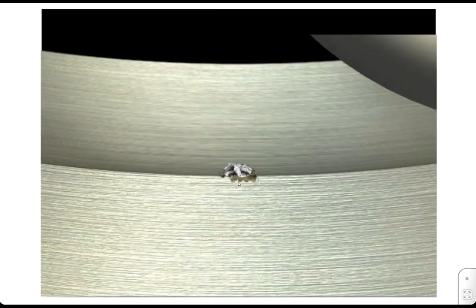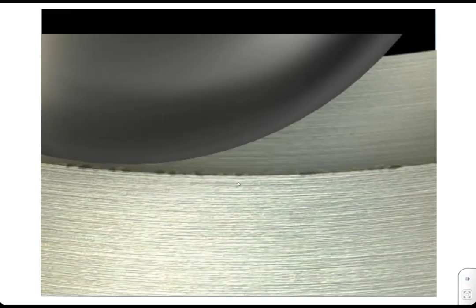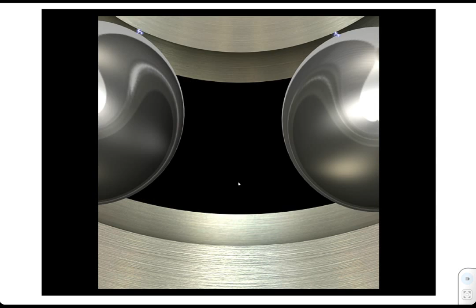Instead of being sort of rolled over, creating indentation, sometimes those little particles can sort of skid along in front of the rolling element, and it sort of scores the surface. It damages the surface, which I hope you can see there. And we can have a situation where there's current passing through the rolling elements. Now this is common with DC drives, but also with variable frequency drives, and that also damages the surface of the bearings and gears for that matter.